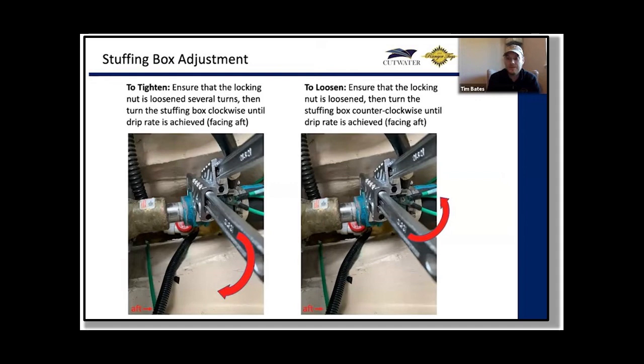So, if we just talked about loosening, to tighten or loosen, once you actually have the backing nut backed away from the adjustment nut, at this point you're either going to tighten to get less of a drip or loosen to get more of a drip. On the left here you have a picture of how to tighten. So once the locking nut is loosened several turns, you can turn the stuffing box or the adjustment nut clockwise towards the back of the boat until you get that drip rate that you're looking for.